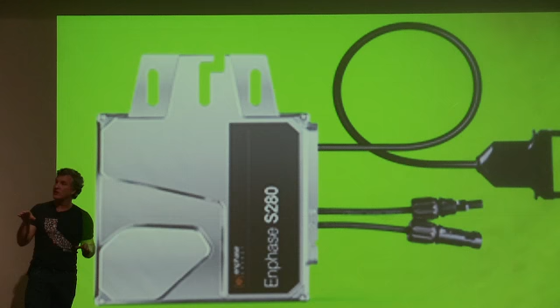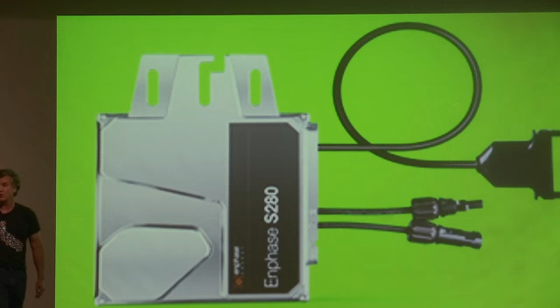So they're working on a new standard for smart inverters to help stabilize the grid. If the grid starts getting stressed, they won't turn off right away - they'll ride through it to help out. Or if they notice a disturbance and need to turn off, they'll ramp down slowly. Utilities can also send signals saying you're producing too much, move it down a little to control it. Through smart inverter technology, we can take renewable energy that's causing grid stability problems and make it part of the solution.